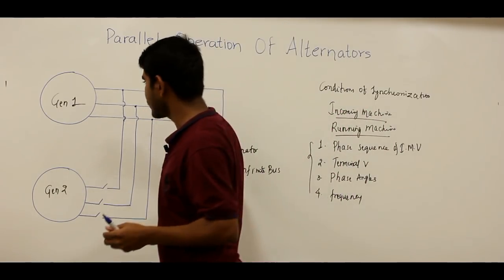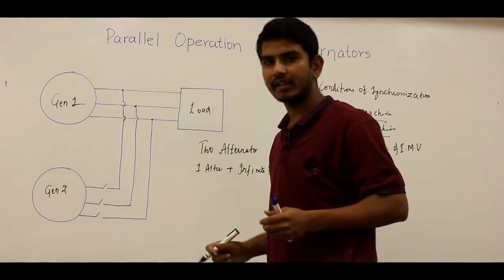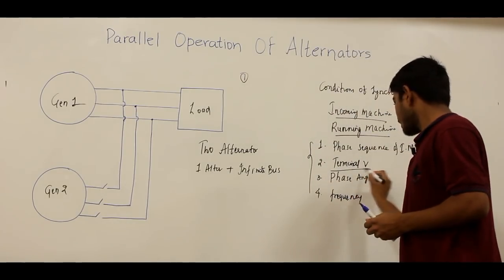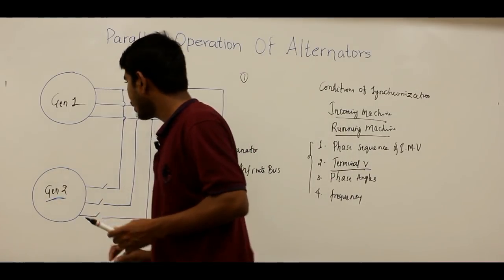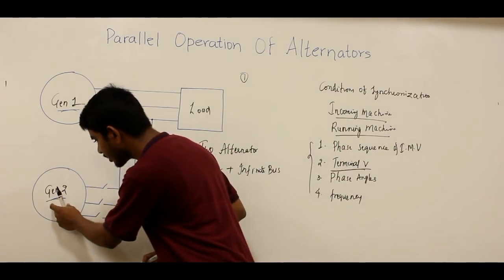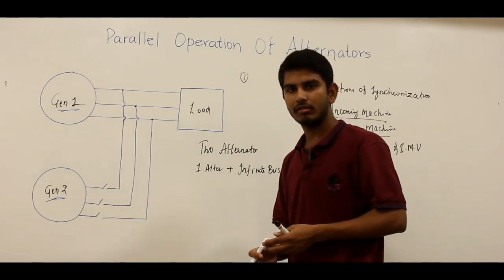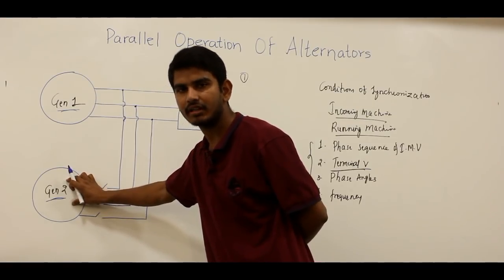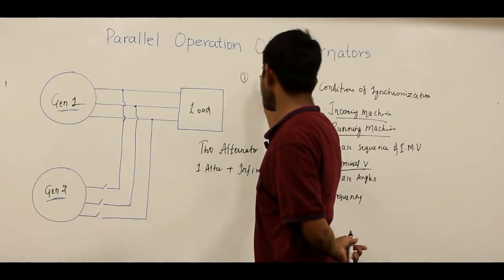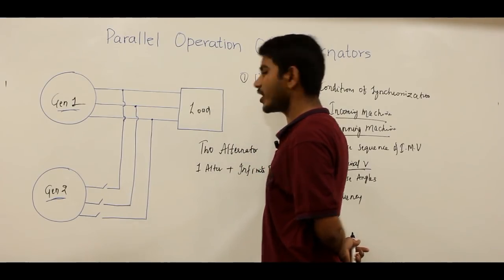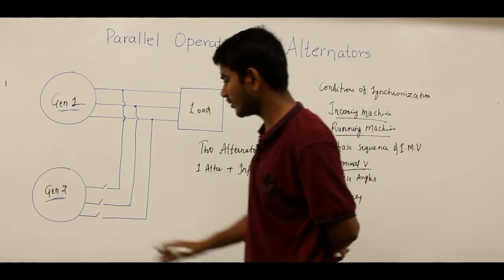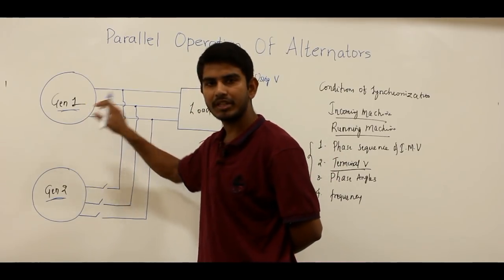The procedure for parallel operation: First, we verify that the terminal voltages of the incoming machine and the running machine are the same using voltmeters. If they are not the same, we adjust the terminal voltage of the incoming machine by changing its field current, making it equal to the terminal voltage of the running machine.